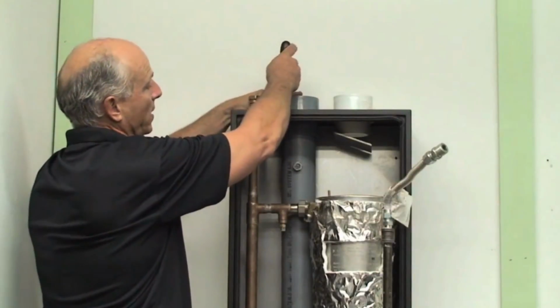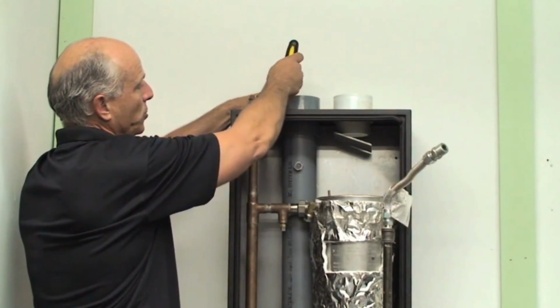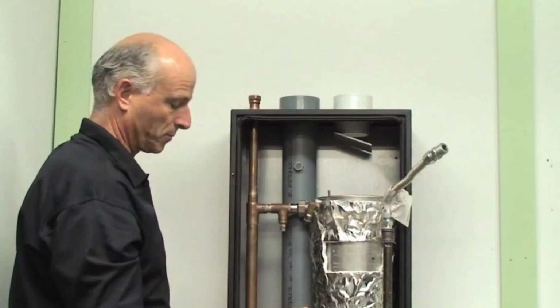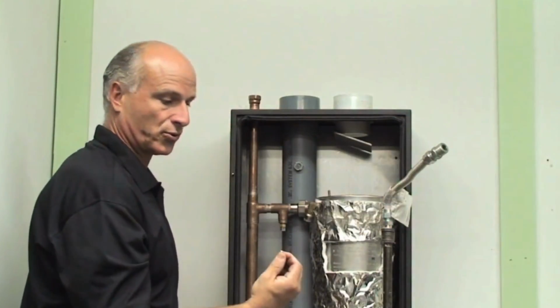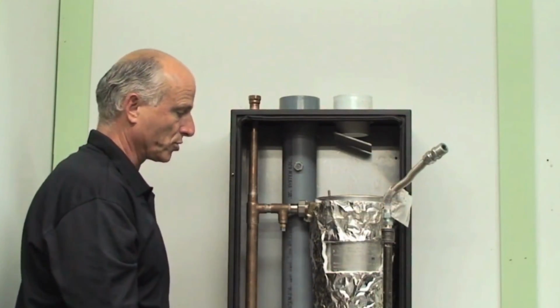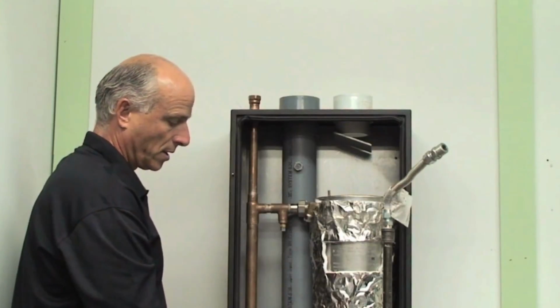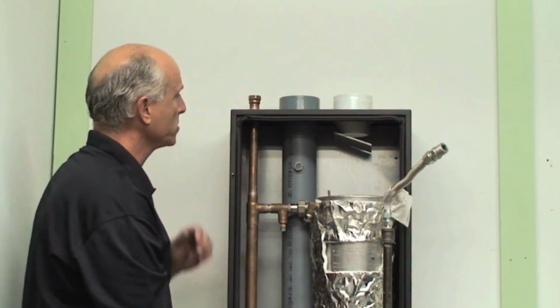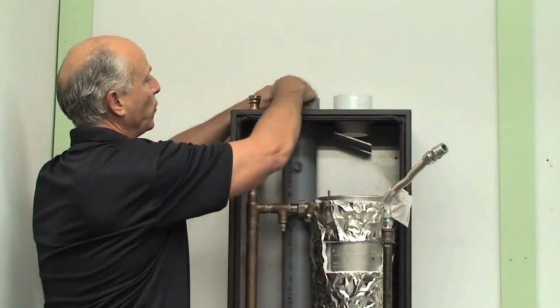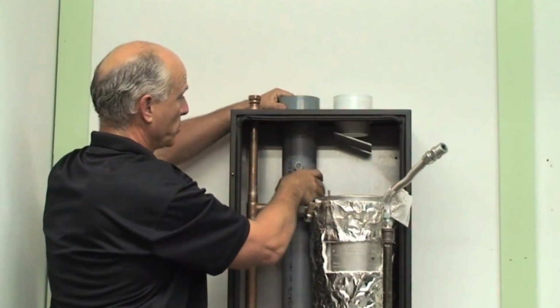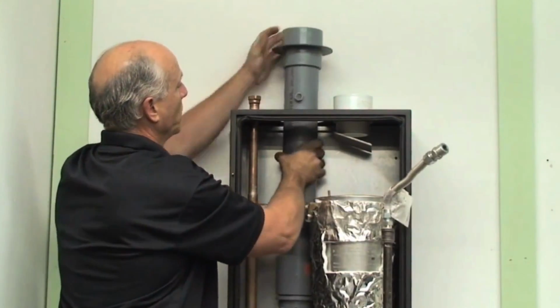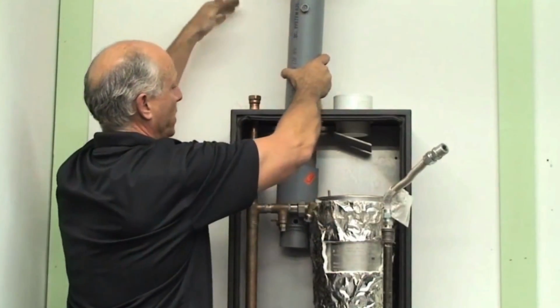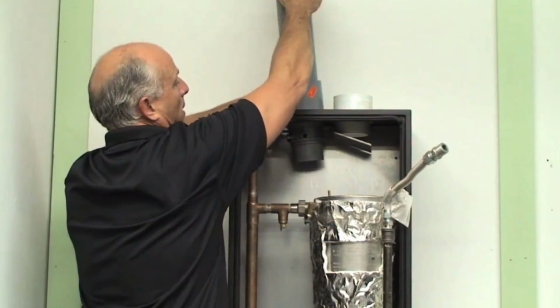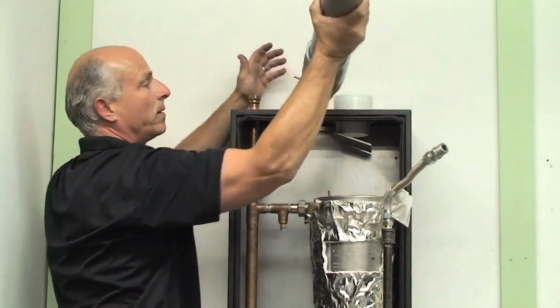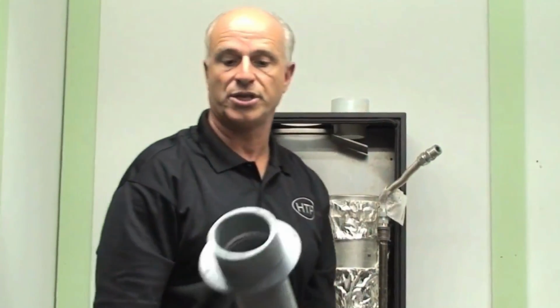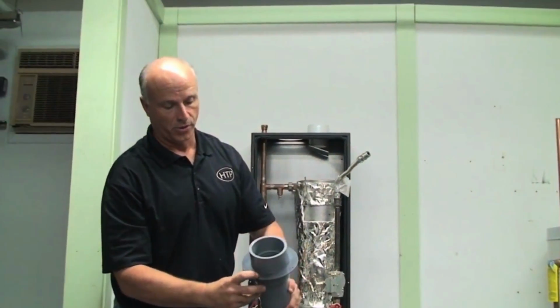Another thing is you can take the flue system out. It's pretty easy to do. Just take the screw with the Phillips screwdriver. Another thing, these screws are the same. So all the screws are the same as I showed you earlier, taking off the panel and other things. To simply take it off, there's 4 screws that hold it. You just lift it up. And obviously you'd have to cut your flue pipe to get it out, but the whole assembly does come out of the boiler. And you can see the assembly with the flange, the holes.